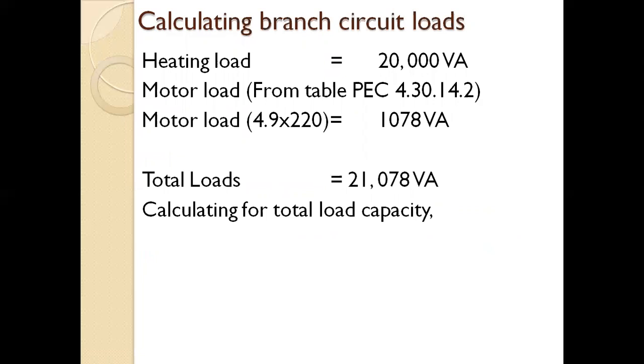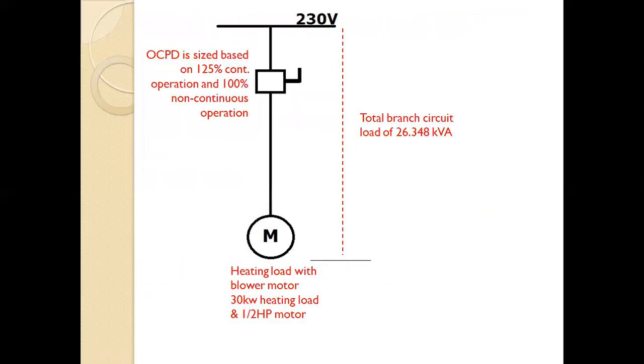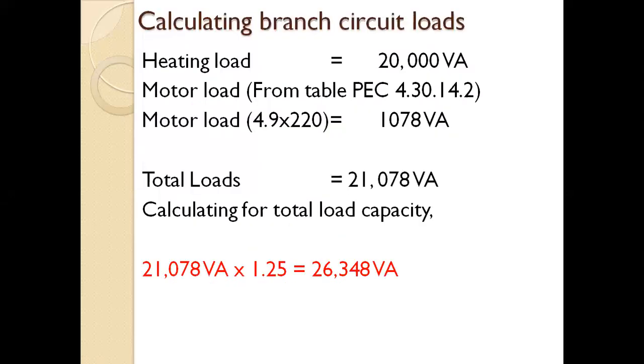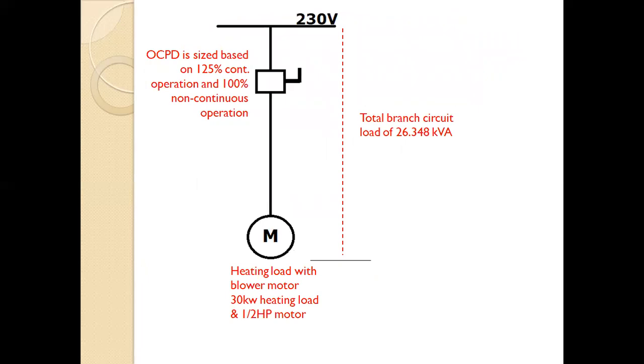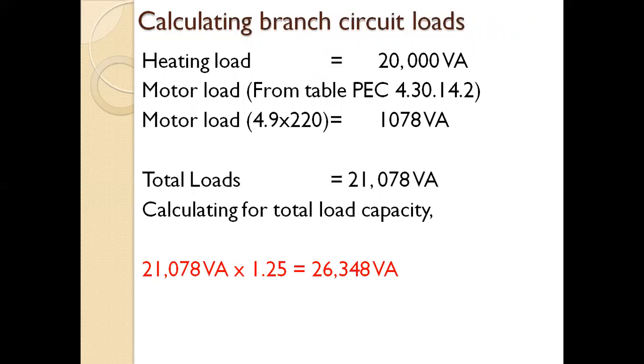Now calculating the branch circuit load. The heating load is 20 kVA. For the motor load, from PEC Table 4.30.14.2, the FLA is 4.9 times 220, so we have 1,078 volt-ampere. The total connected load is 21.078 kVA. Multiply by 1.25, since 125% is for continuous load, so we have a total of 26.35 kVA.